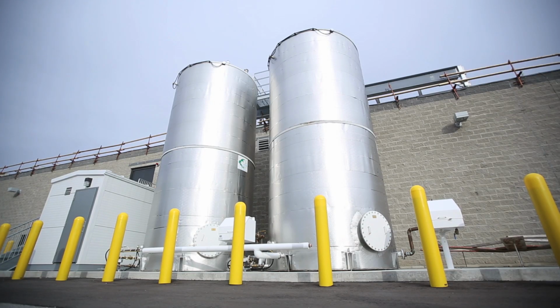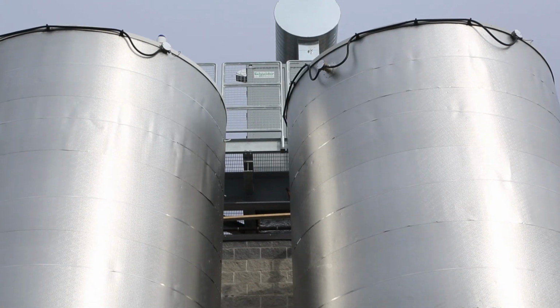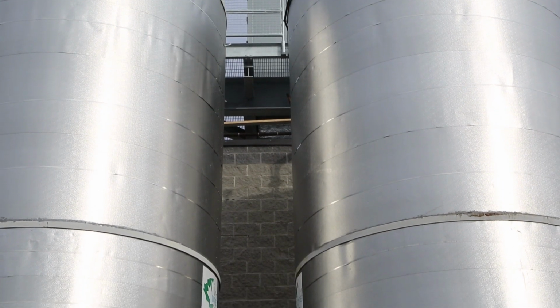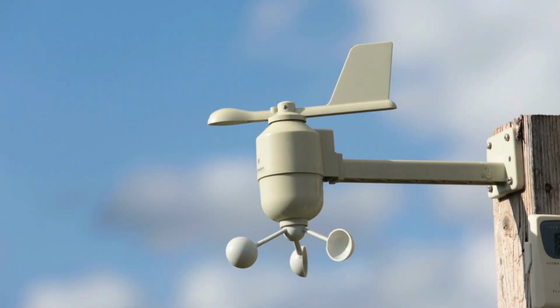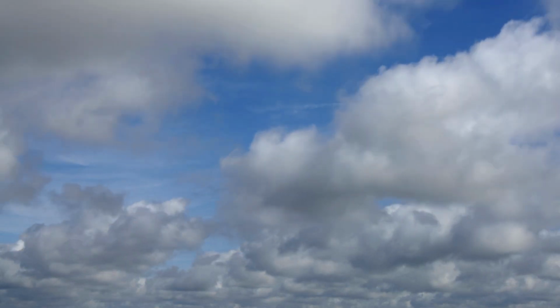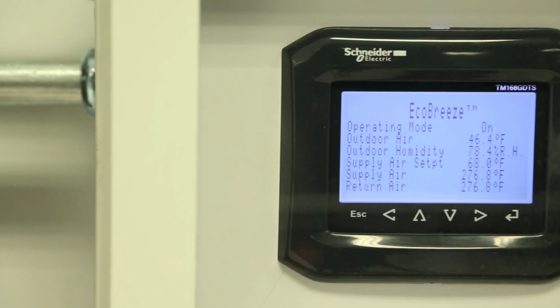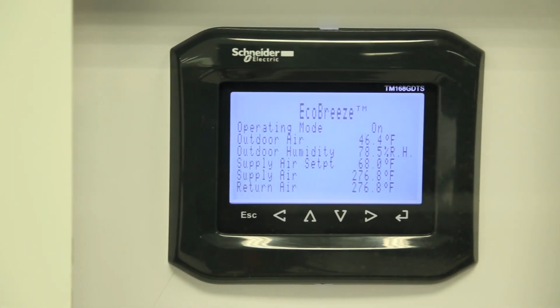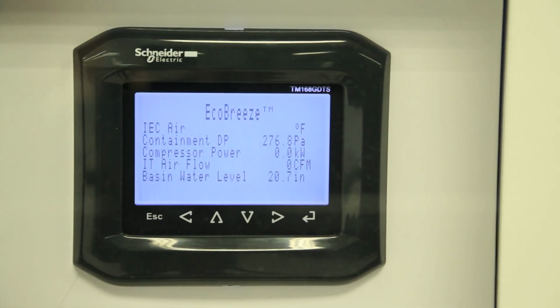EcoBreeze has a distinct advantage in that it uses less water than a typical cooling tower and chiller plant. Especially here in Barrie, Ontario, where we can take advantage of the cooler, drier conditions outside of the building, the EcoBreeze system can often run in a dry mode of economizer, which uses absolutely no water.